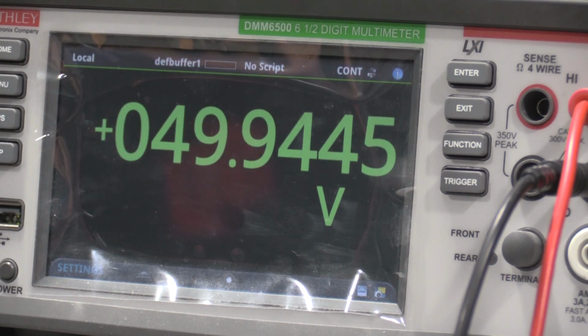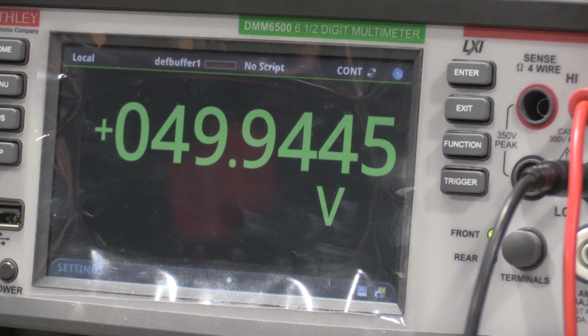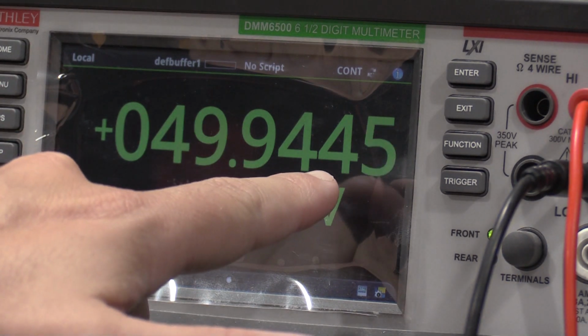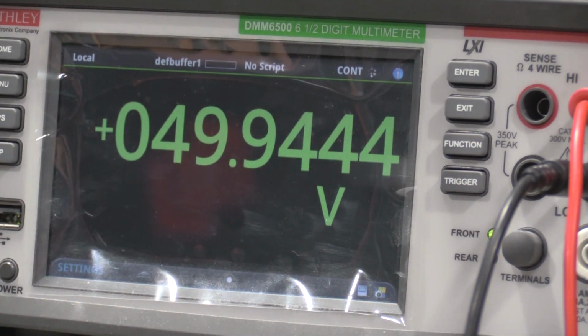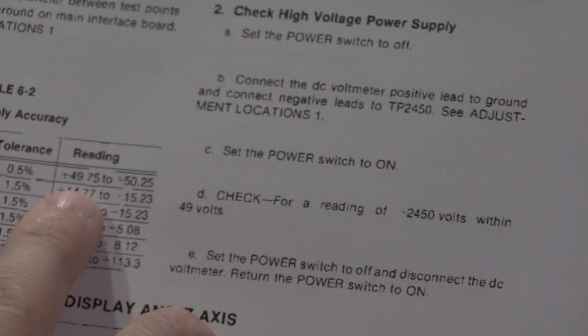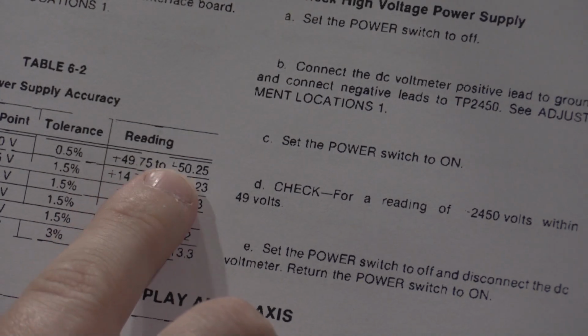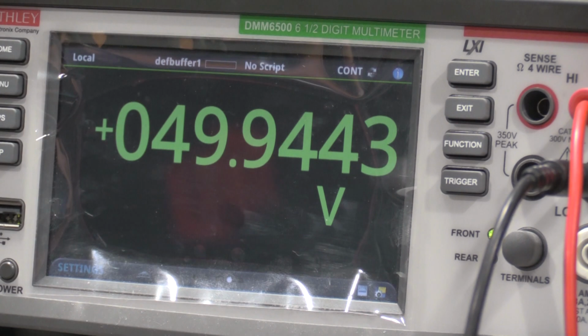In this particular case, it's almost not worth adjusting because it's off by 5 millivolts. Actually, we don't need to adjust it because there's a note in the service manual. If the 50 volt supply is within specified tolerances, you don't need to adjust it. So we actually don't, because my tolerance is 49.75 to 50.25, and we're at 49.94, so we can leave that one alone.